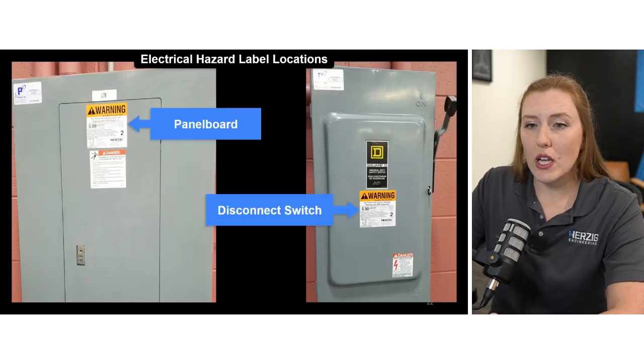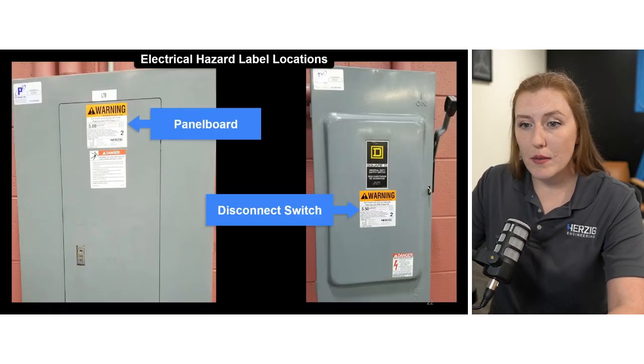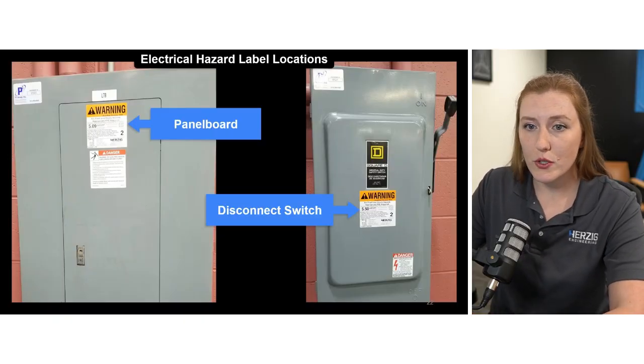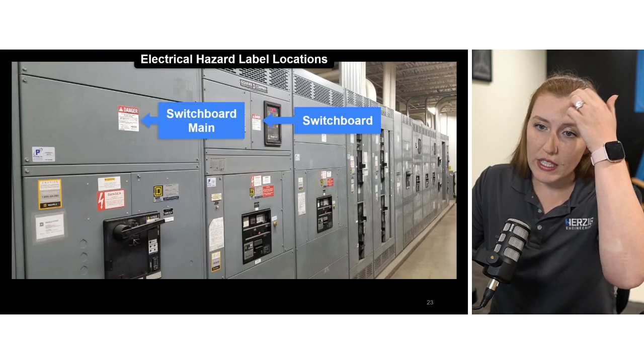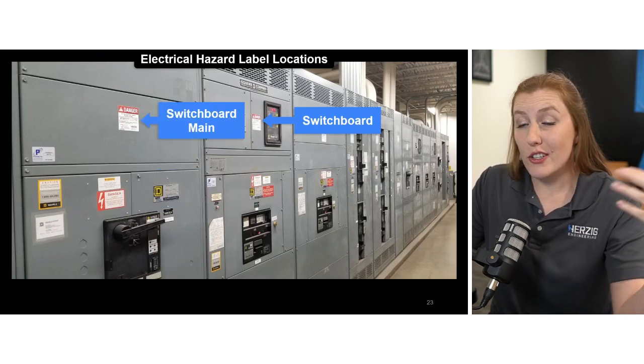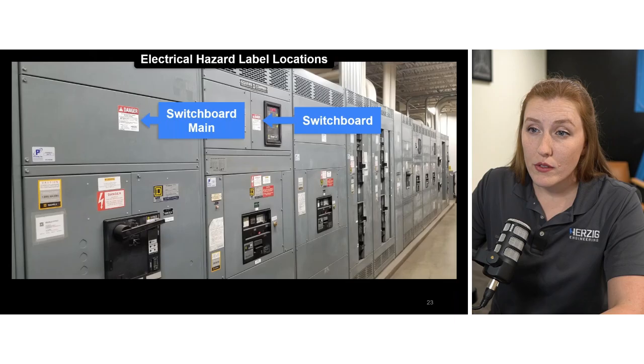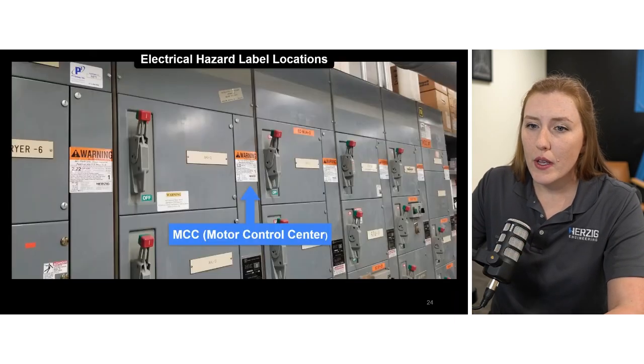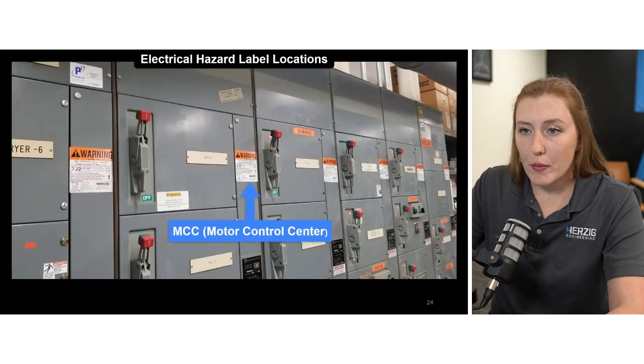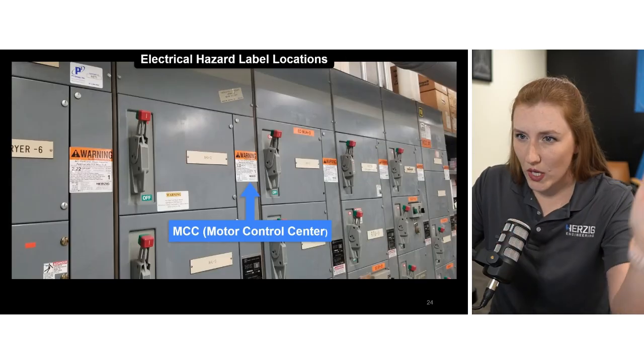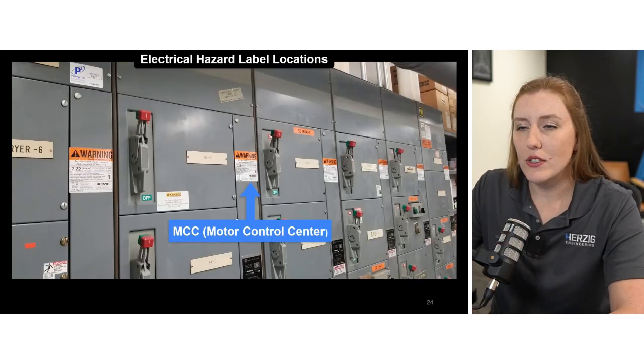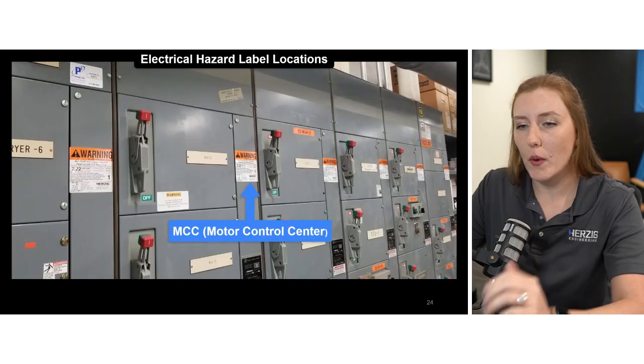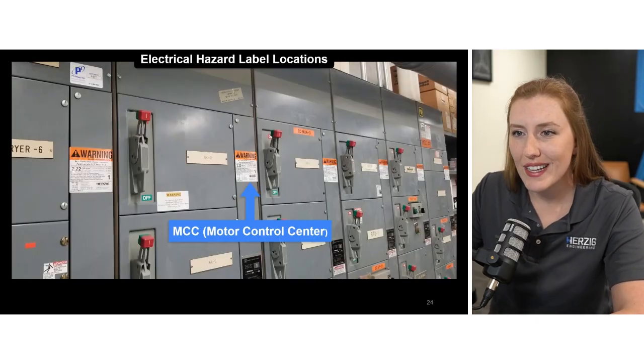So those labels go on everything that was included in the study, basically. So the panel board, the disconnect switches, all of those throughout your facility, switch gear, switchboards. There's usually a label per section for those, so you have to be careful about where those go. Motor control centers, we put several labels, one per column, just to make sure that it's easy to find. Could be at the top, could be on the wireways. That's kind of a judgment call for you guys to make.